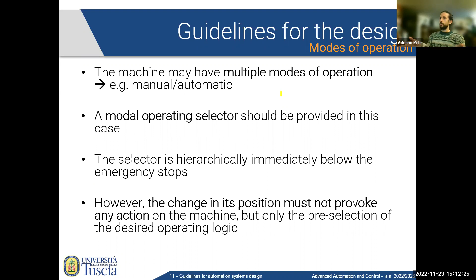Imagine you have a mode selector which switches from manual mode to automatic mode, for example. It's not that this mode selector does something on the machine directly - it's just giving information to your controller, which takes the measurement of the position of the switch and decides how to operate the machine based on the mode selected by the operator.